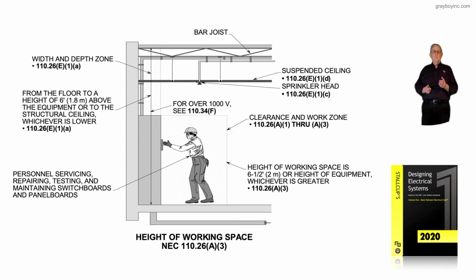Now reviewing that 6 foot rule, notice there's a suspended ceiling there, which is permitted by 110.26(E)(1)(d), as in dog. Then also notice the sprinkler head is permitted there in accordance with 110.26(E)(1)(c). And that's all. But now we could have a transformer located above that equipment if it's not foreign to the equipment. We've kind of gone through the slides and talked about that.